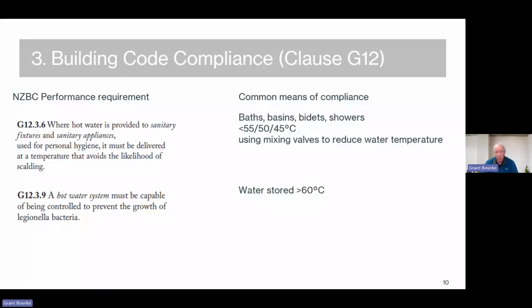So we, as always, store water at 60 degrees. Any water going around the ring main at less than 60 degrees, we need to clean that up via a UV sterilizer before we send it around the ring main again. So a big one here, building code compliance, all components must be suitable for potable water.